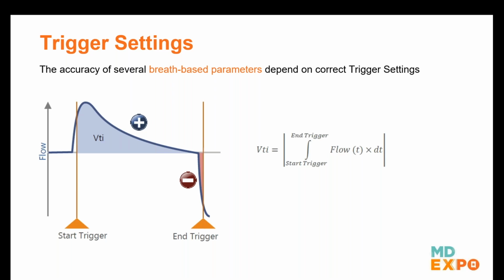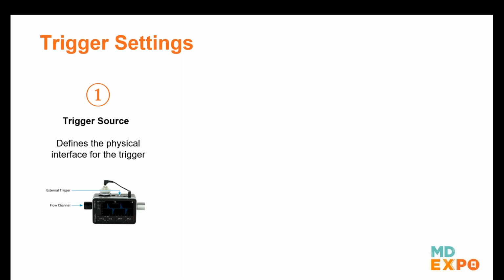Yep. So the question, before we talk about how we find the best trigger settings in a specific application, let's talk about some basics. Trigger settings are always defined by 3 main parameters. The first one is a trigger source. There are different sources we can use for triggering, typically with a gas flow analyzer. It could be just a flow channel of the analyzer. It could be a pressure port as well, or it could also be a digital signal generated by the ventilator, and you connect a digital cable to the analyzer, and this triggers the breath cycles.